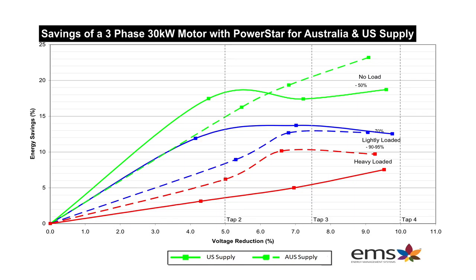Here we have a 30 kW motor bench test, direct on line, with a 9% voltage reduction using Australian voltage. With a no-load motor, we see a 23% energy saving. At lightly loaded, still 13% energy savings. Even at heavily loaded, just under 10% energy savings. The average energy savings we see across full facilities — whether a hospital, cold store, or high-rise building — is between 12 and 15%. Some cases go above 20%; some are at 8%, but those ROIs are still good due to high kilowatt-hour costs and high consumption.